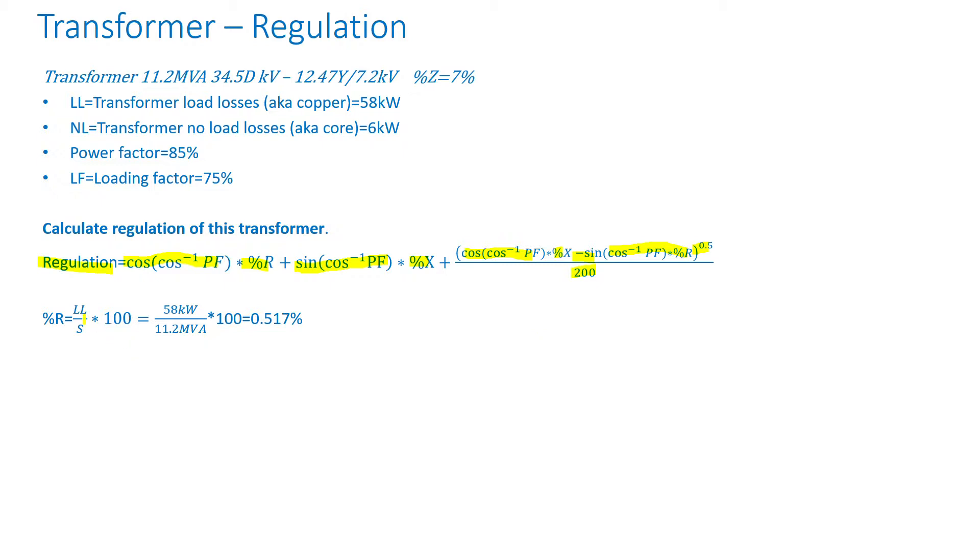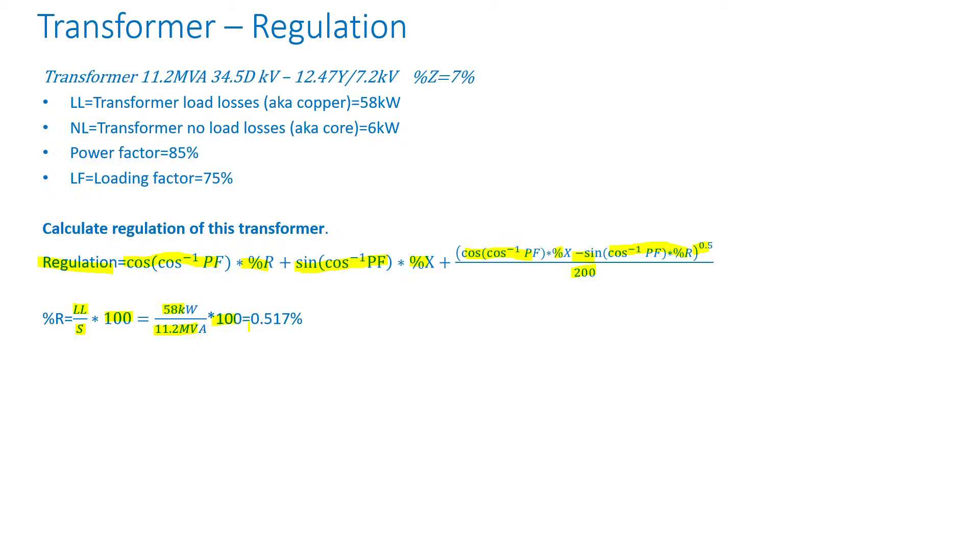Percent resistance is just load loss divided by apparent power times 100. In our example, load loss is 58 kilowatts and apparent power is 11.2 MVA times 100. Pay attention to units. Kilowatts, K means times 1000, MVA, M means times 1 million. So you want to make sure you multiply the factors properly. Otherwise, you're going to be off by a big factor.